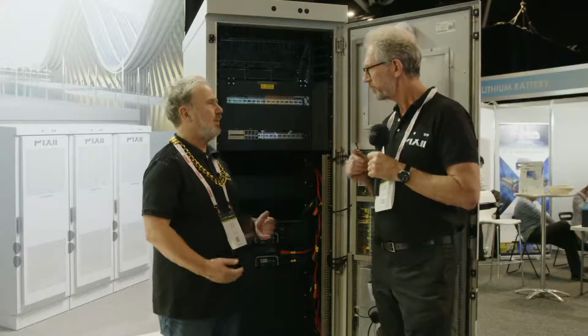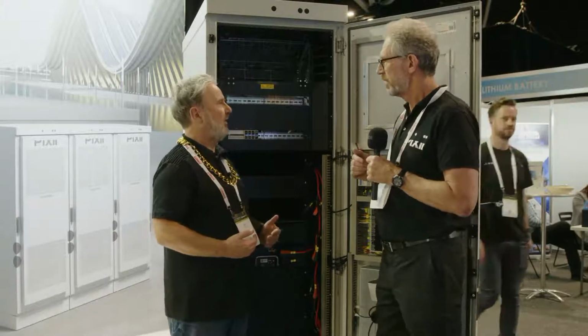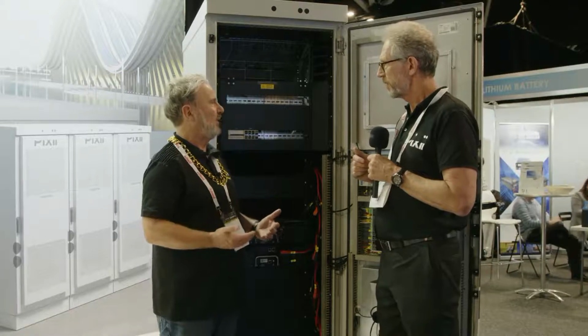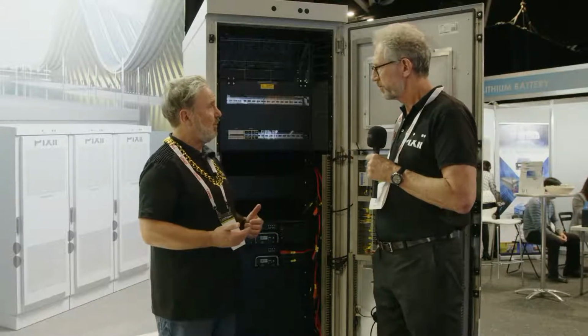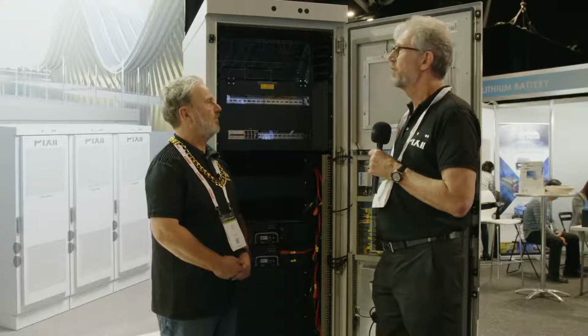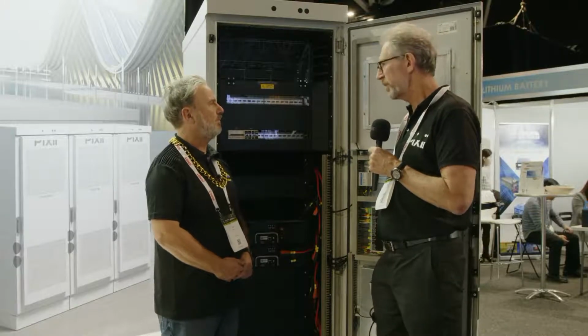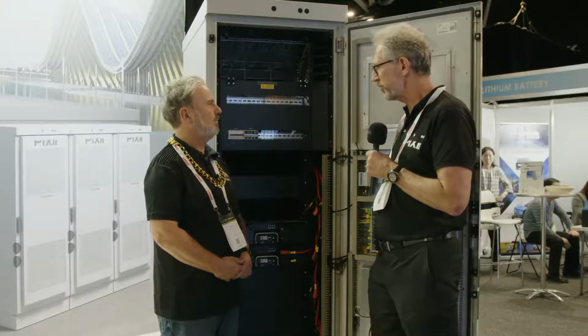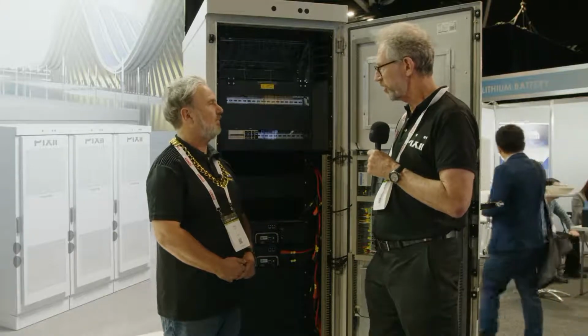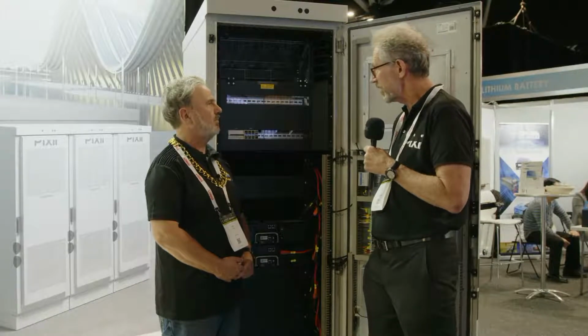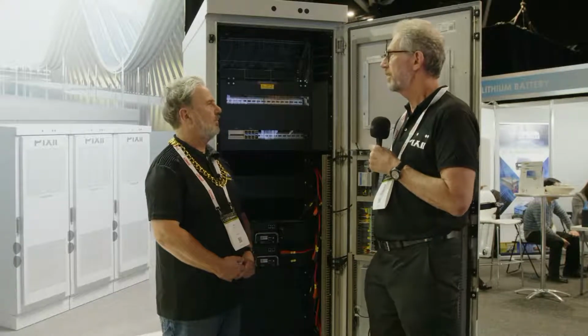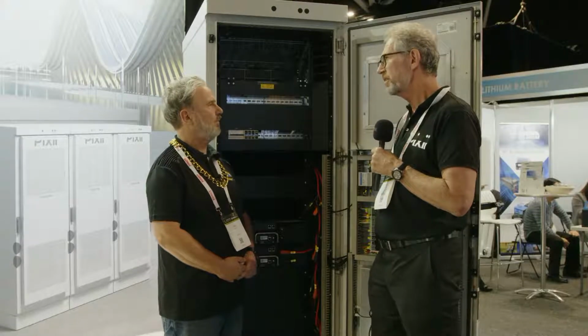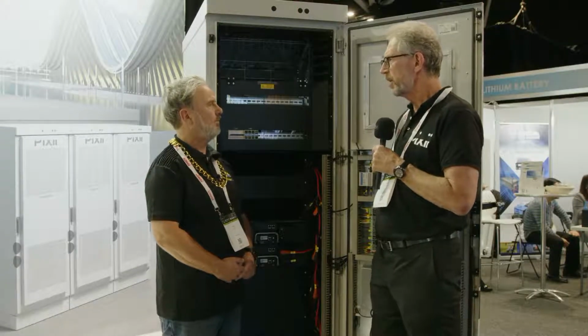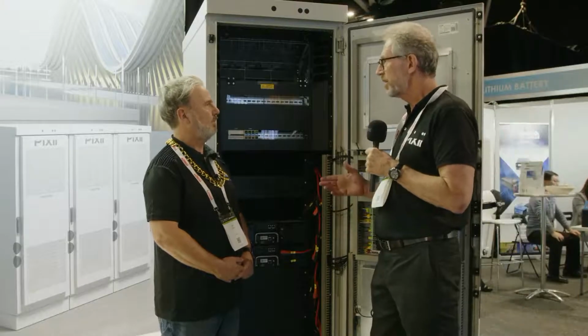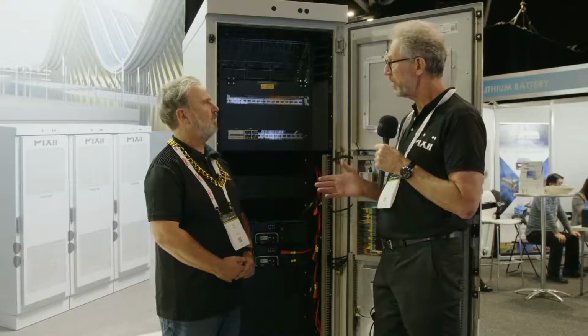For telco applications, I imagine it would be a standalone product, like a UPS system for backup when the grid fails, but you can also support the grid now. That's right — in a telco application, they typically use rectification to provide power during a failure to their telecommunications loads. This system works in that scenario perfectly well as a rectifier, but it also gives telcos the opportunity to use their lazy asset, the batteries, to provide arbitrage services back to the utilities.